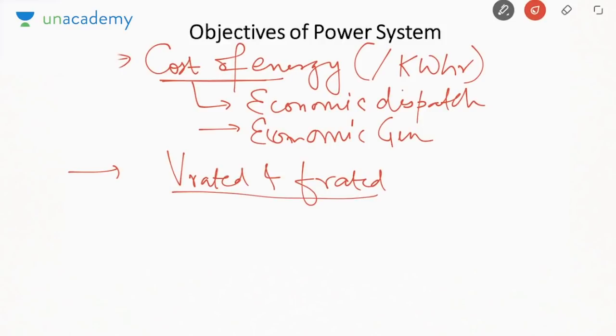So to meet this objective, we study about automatic voltage and frequency control. Now usually the frequency depends on the speed of prime mover in case of synchronous generator. That means to control the frequency, we must control the speed of prime mover for a synchronous generator. And to control the voltage, we can either control excitation EMF, or we can use the reactive power compensation that we'll see later on to control the voltage at any bus or any terminal.